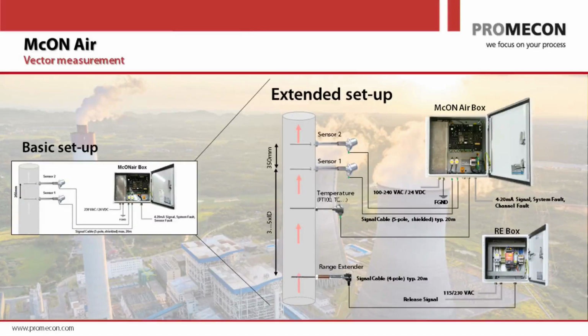You can also see a temperature measurement device installed here. We recommend that this device is not connected to our box, but connected to the DCS, where you also have your barometric pressure and the geometries of your duct. And the big advantage of that is that you have all these specific parameters, such as area of your duct, temperature of that duct, as well as pressure, in your DCS. So there's no programming necessary for our box. Our box only gives you velocity, that's it. So you can change our box from measurement location to measurement location without reparametrization. The box always holds the same parameters. There's absolutely no problem. Therefore, we recommend that you only have the sensors hooked up to it.